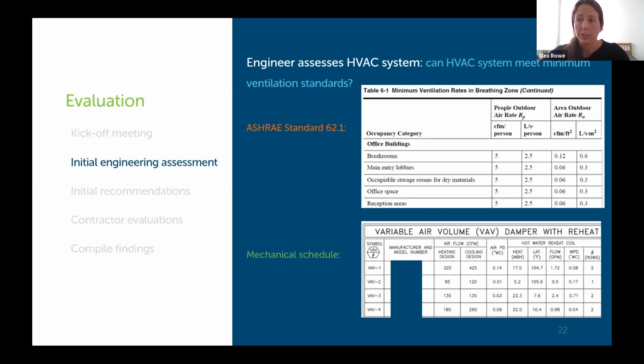Next, the engineer dove into their initial assessment where they calculated how much ventilation would be required based on the area of the building and the number of occupants. So as Rachel mentioned earlier, ASHRAE standard 62.1 provides the minimum required ventilation by building type. So this is an office space, and they required 5 CFM per person and 0.06 CFM per square foot for all of these different types of office building spaces. So that's that minimum requirement that the engineer will be comparing to.